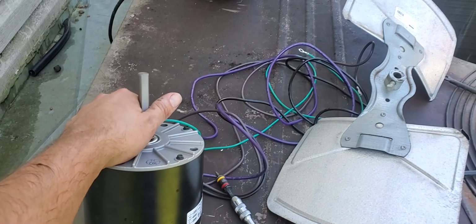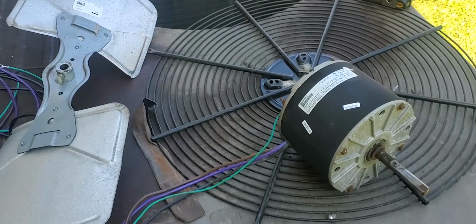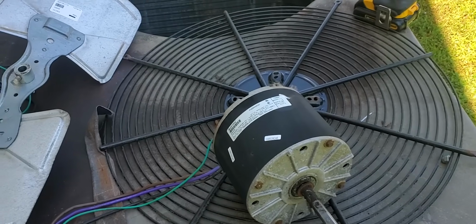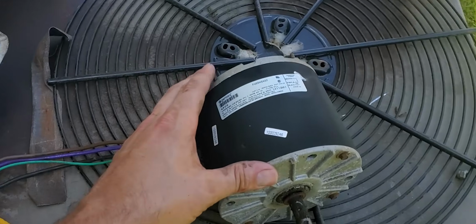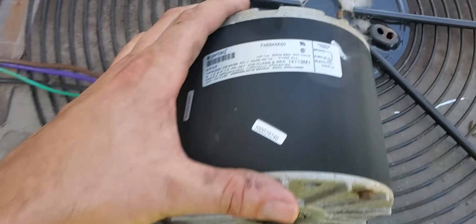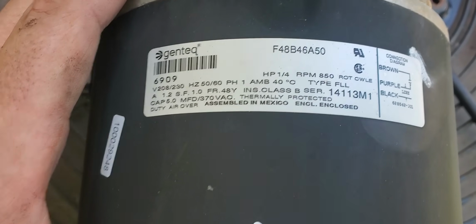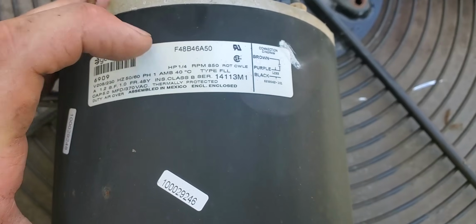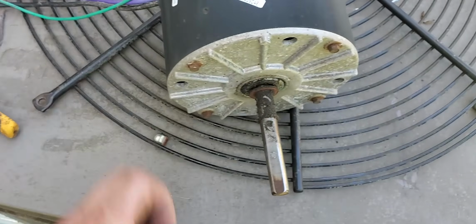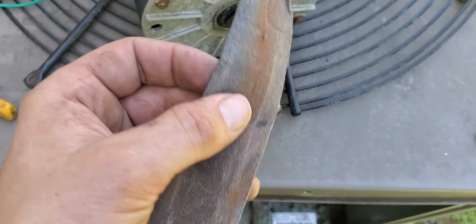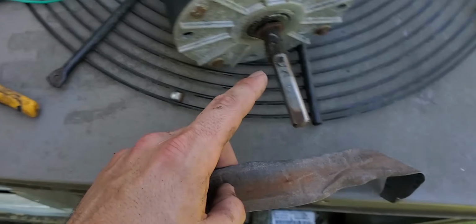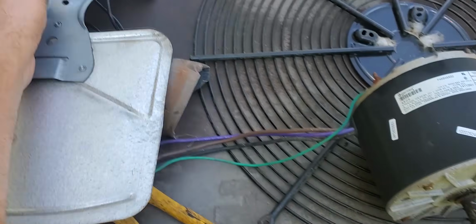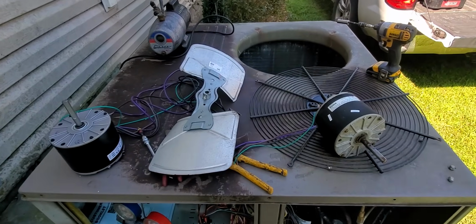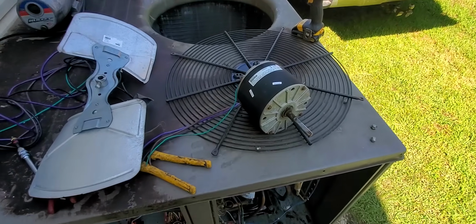I wanna show you right now the most replaced motor. This is the most replaced motor in my opinion. I have replaced at least 100 of these motors on these York units. Motors made by Genteq, and it is a 1/4 horsepower 850 RPM condenser fan motor. Had to get some sandpaper to sand the shaft to get the actual hub to come off of the shaft. So make sure you have some sandpaper with you. Definitely need some sandpaper. All right, so I'm gonna vacuum it down. First, I'm gonna replace this motor.